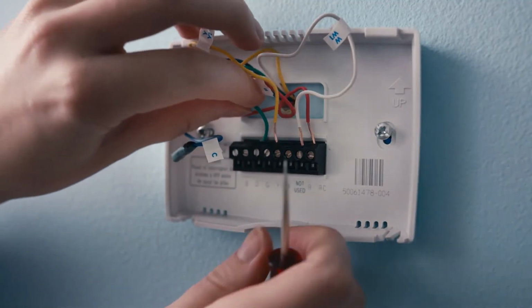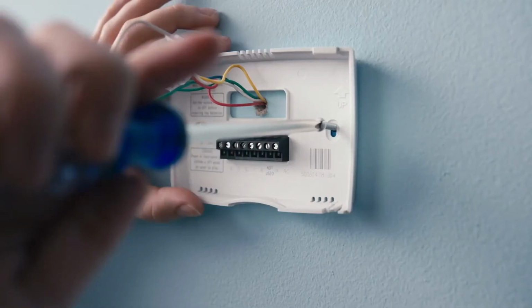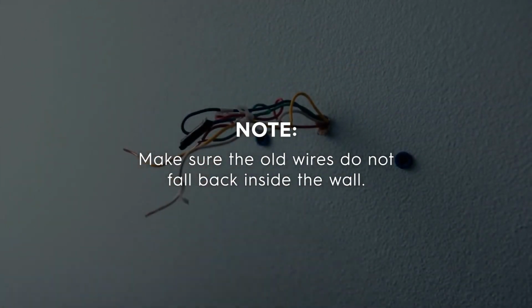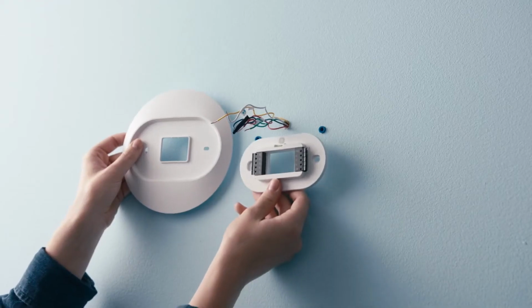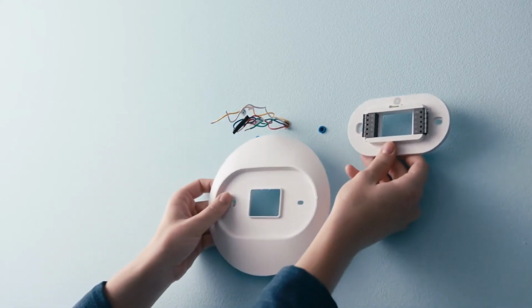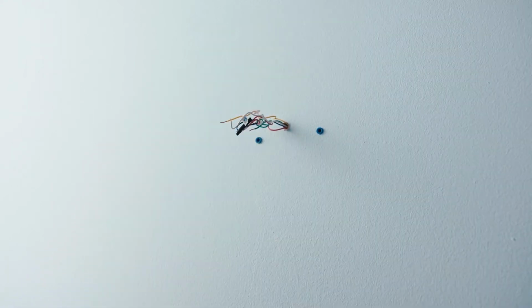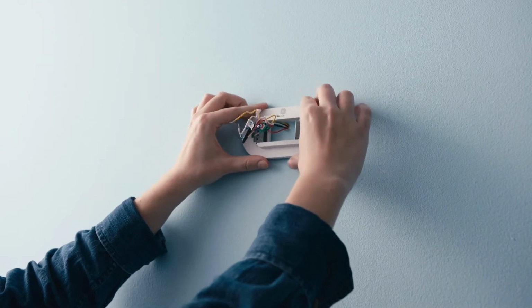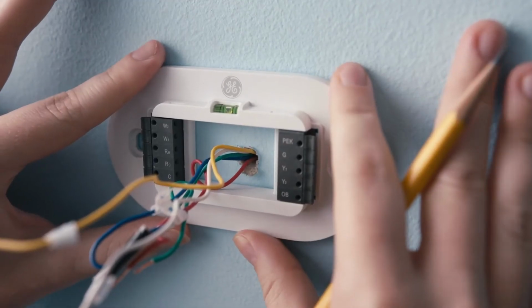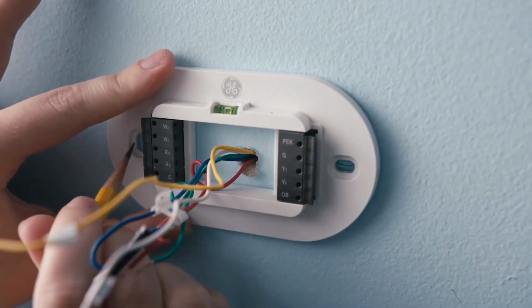Step 1. Disconnect the remaining wires and unscrew the old thermostat base. Make sure those old wires do not fall back inside the wall. Step 2. Decide if you need to use the provided trim plate. If you decide not to use the trim plate, simply place the back plate against the wall. Make sure it's level using the built-in level, and mark both holes with your pencil.